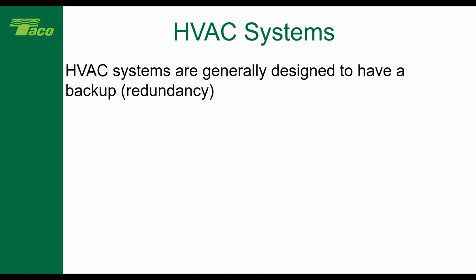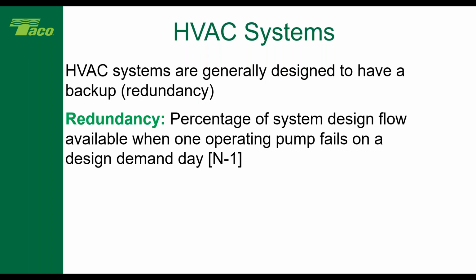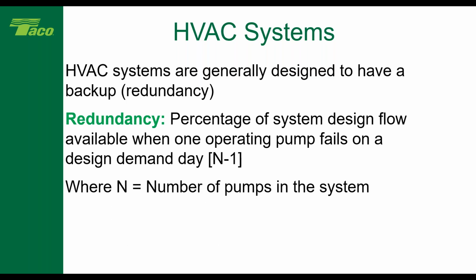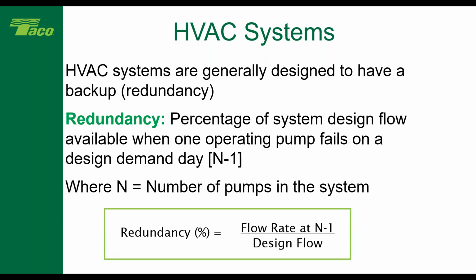So we know that HVAC systems are designed to have a backup most of the time. When I look at pumps, redundancy is a little bit different. Redundancy is the percentage of system design flow that is available when one operating pump fails on a design demand day, or N-1, okay? Where N is the number of pumps in the system. So redundancy percentage is equal to the flow rate at N-1 divided by the design flow.